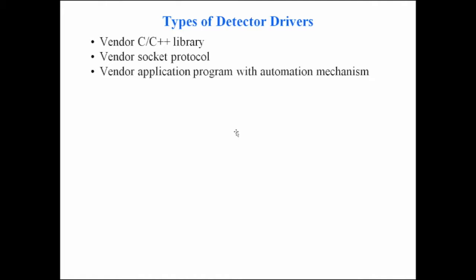Now I'll talk about drivers. There are really three different types. If you're writing a new one, the best approach is to find one using the same mechanism as what you want to write. The three models are: the vendor provides a C or C++ library you call; the vendor gives you a socket server with a defined socket protocol; or the vendor gives you an application program with some way to automate it.